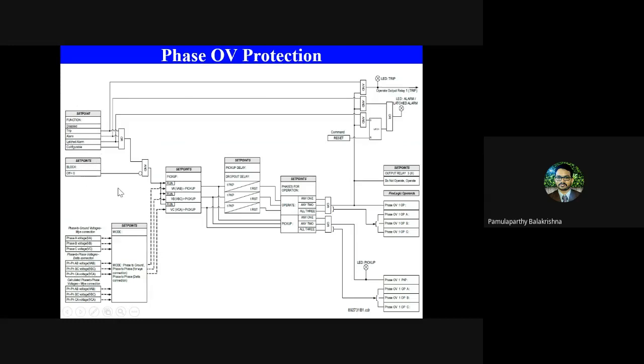Once this is clear, in order to execute the overvoltage function, we need voltage. So from where will that voltage come? Voltage will come from the VT. Again, that VT can be delta type or star type connection, so it can be line to line voltage or line to ground voltage. All those computations will happen, and based on the user specification, whether to use line to ground or line to line voltage, the particular voltage measured by the relay is taken as the input and will come to the logic. So what is the logic required here? To check whether the voltage is greater than the pickup or the threshold that is configured, to call it an overvoltage function. If there is an overvoltage in the system, it will impact basically the insulation of the equipment.